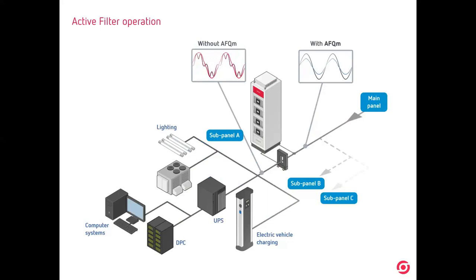Remember AC/DC. See the sinusoidal wave. Now it's not sinusoidal, okay? And this can create the damages that we have seen. So if you install an active filter upstream, you will clean the sinusoidal wave. When I say clean, we will make the current and the voltage sinusoidal, the wave more sinusoidal. Okay, so in sub panel B, in sub panel C, in the main panel, or in the power transformer, you will have a clean waveform, okay, not affecting the processes, not affecting the cables, etc.